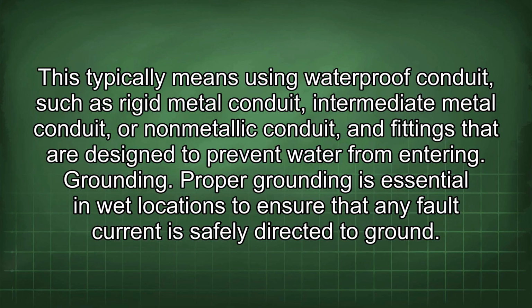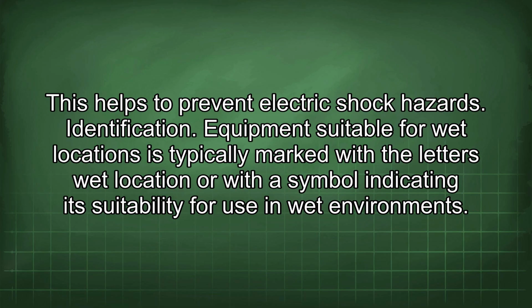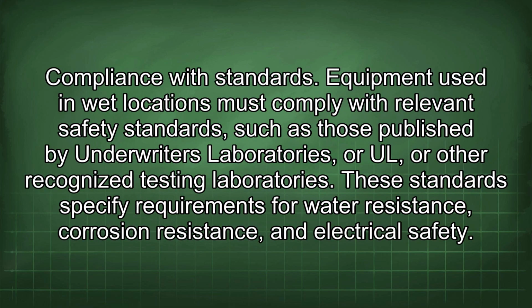Grounding. Proper grounding is essential in wet locations to ensure that any fault current is safely directed to ground. This helps to prevent electric shock hazards. Identification. Equipment suitable for wet locations is typically marked with the letters wet location or with a symbol indicating its suitability for use in wet environments. Compliance with standards. Equipment used in wet locations must comply with relevant safety standards such as those published by Underwriters Laboratories or other recognized testing laboratories. These standards specify requirements for water resistance, corrosion resistance, and electrical safety.